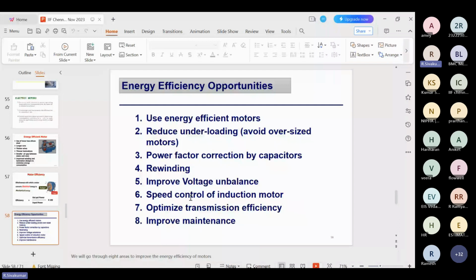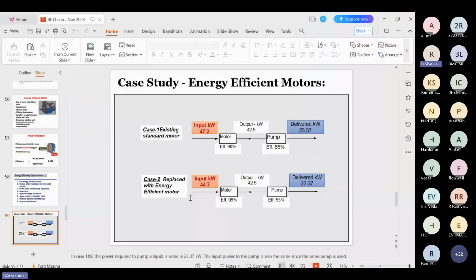In the final slide, I put one example here, and improve the maintenance activities. This is one case study in energy efficient motors. Consider a pump application. One motor with 90% efficiency is connected. The pump efficiency is 55%. The process delivered power is 23.37 kilowatt, whereas the pump efficiency is 55 and the motor efficiency is 90.